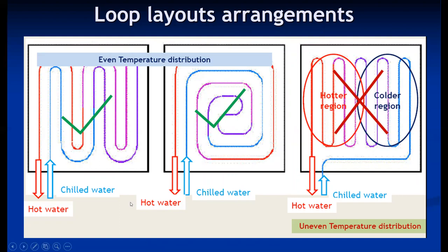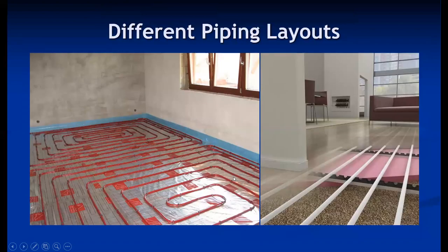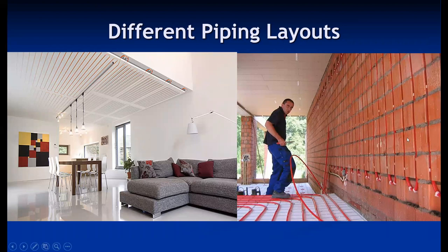These are the recommended loop layouts, which give uniform temperature everywhere. Inlet at one side and outlet at the other in a simple configuration creates hotter and colder regions, which is not recommended. Whatever layout is used, the loop should provide uniform temperature distribution. Both recommended configurations provide uniform distribution of temperature. Different layouts can be used in practice — radiant piping can be installed on the side wall, ceiling, or flooring.